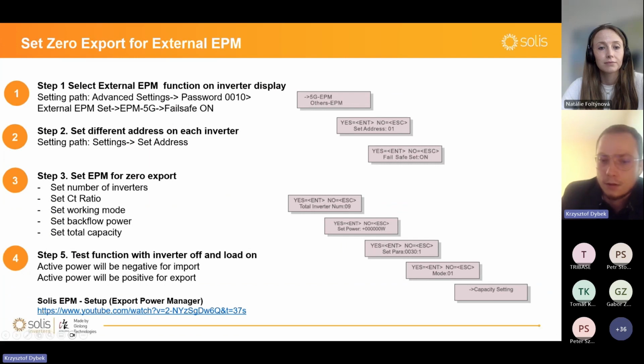Yeah, and this is just a few words about how to commission those grid-tied inverters. So we have two paths. First path is to go directly to the inverter. Each inverter, go to advanced settings. Password is always 0010. So you need to use external EPM set. EPM 5G and failsafe needs to be on.